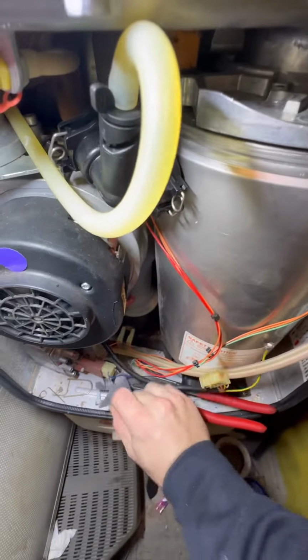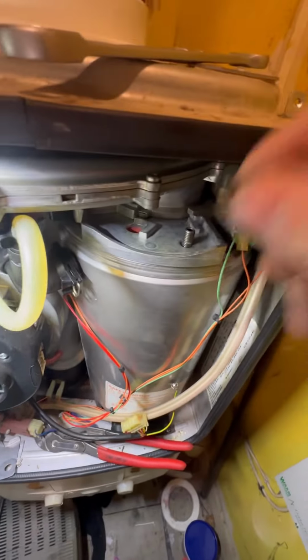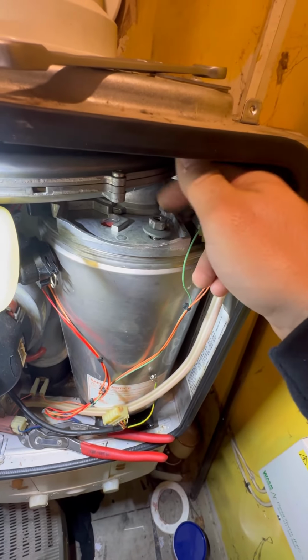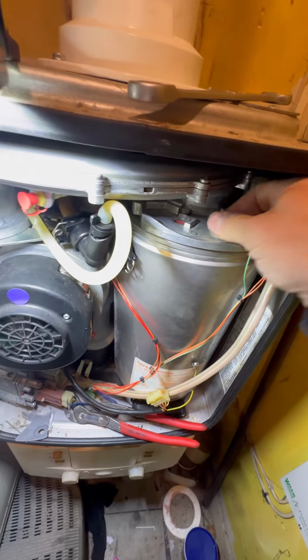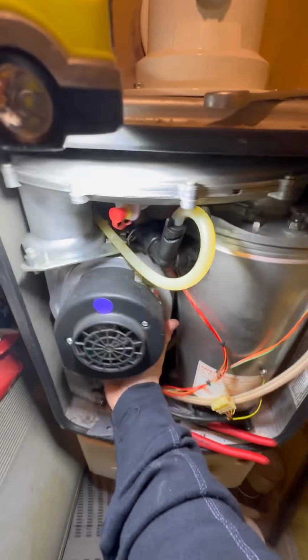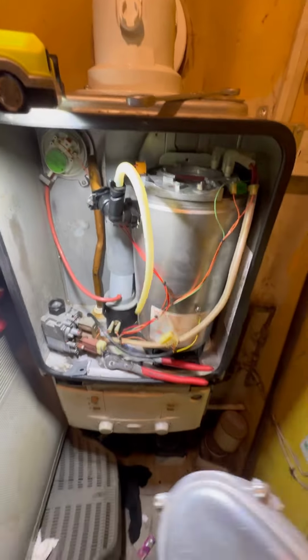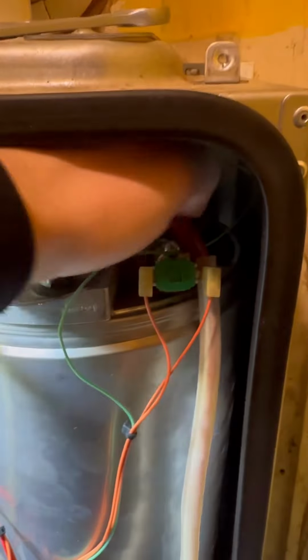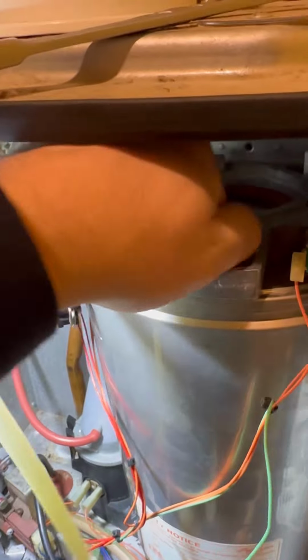If you watch my other videos, you know I take the supporting clamp off and then I put the 13mm nut back on and tighten it up, and it makes it easier to whip the manifold out. So easy, I'm doing it one-handed. And then with that plate clamped down, it makes it easier to get the electrodes and the flame rectification off. They can be a bit fiddly, but just twist them and they'll pull off. Now I take the 30mm nut off.